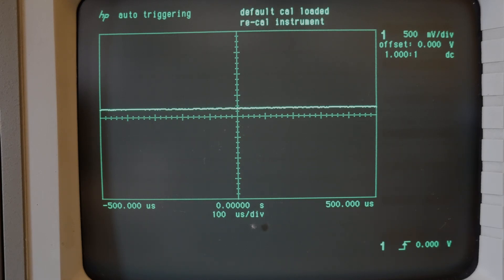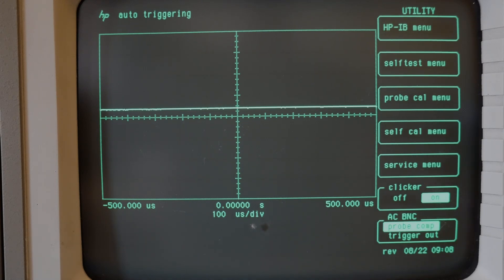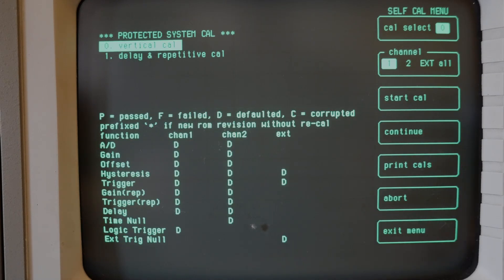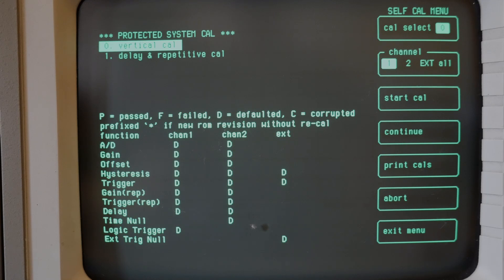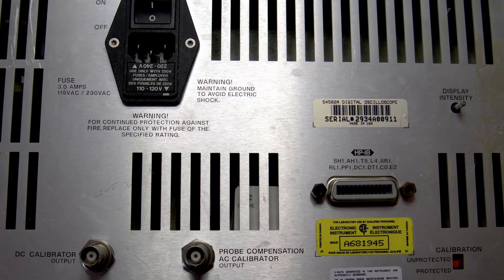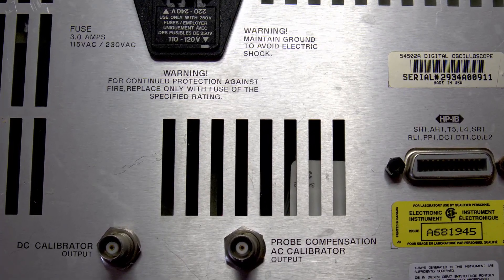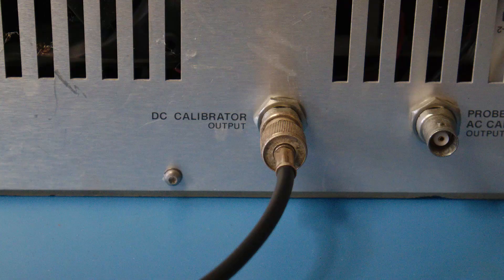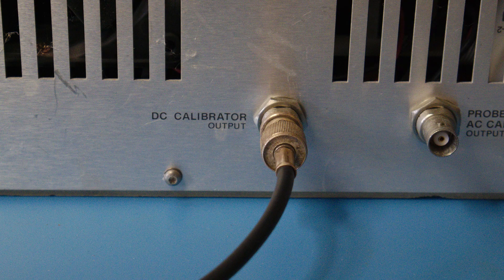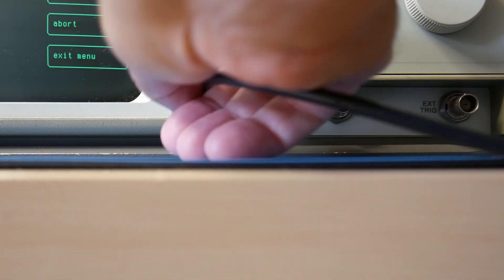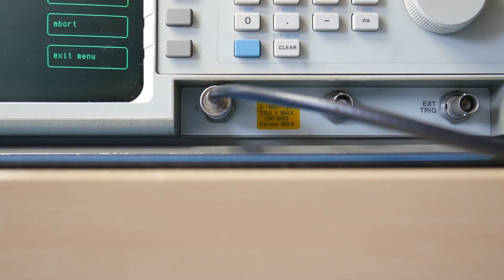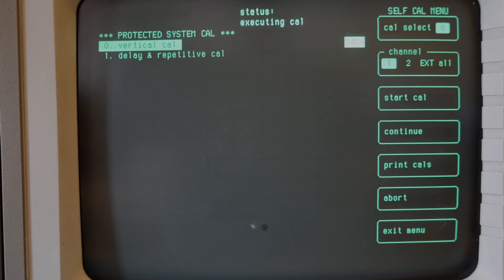But let's see if we can calibrate the instrument. So I'll select the utility menu here and self Cal menu, and we will select Cal zero channel one and say start Cal. It says connect the DC Cal rear panel BNC to the input channel one. So I'll do that right here. I have that cable connected on the back already. I'll put it into channel one here and then press continue and it will execute the calibration here.